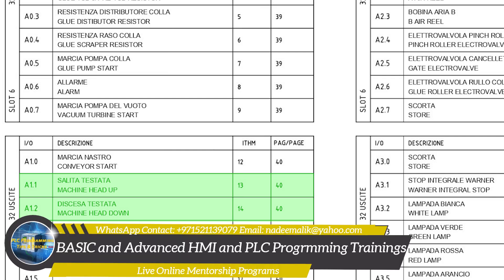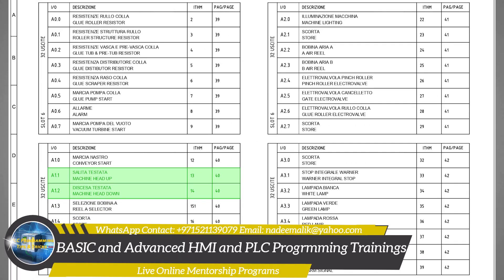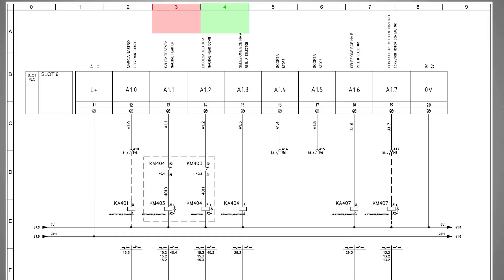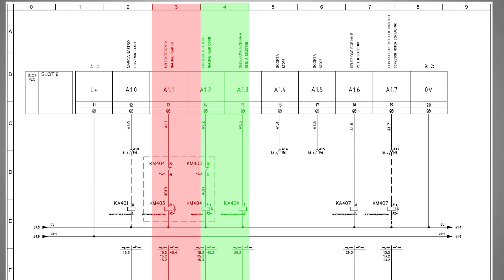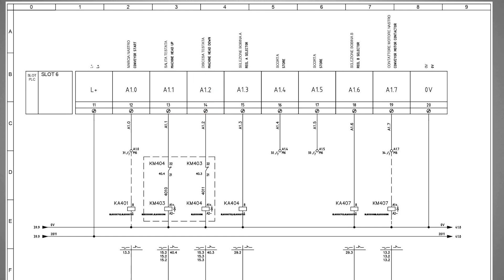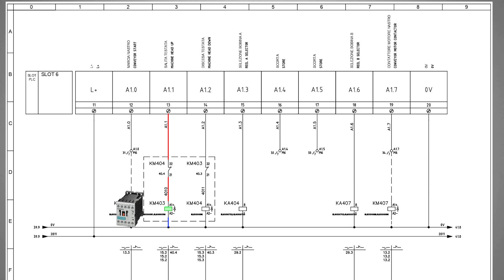You can find outputs A1.1 and A1.2 on page number 40, in column number 3 and column number 4. Terminals 13 and 14 are for A1.1 and A1.2 outputs respectively.